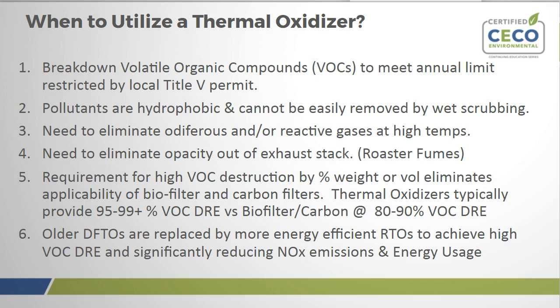Another thing to consider, if it looks like we have many experts and probably people that have older oxidizers at their plants here attending, but a lot of the older DFTOs, the direct fired afterburners and recuperative units, they typically use a lot more energy than RTOs. And RTOs can be retrofitted on them to achieve higher destruction VOC or equal high VOC destruction. And they can also reduce these NOx emissions and also the energy usage, which is key because energy costs are only going to go up in the future.